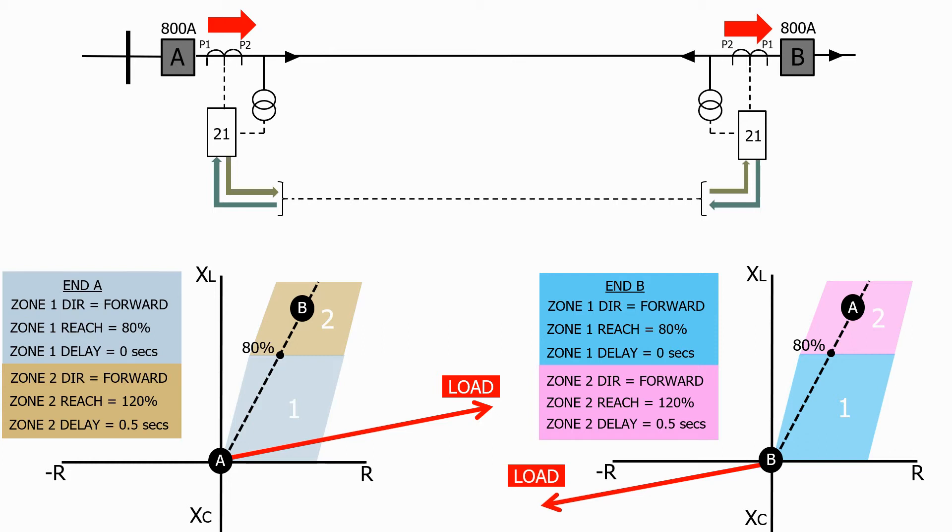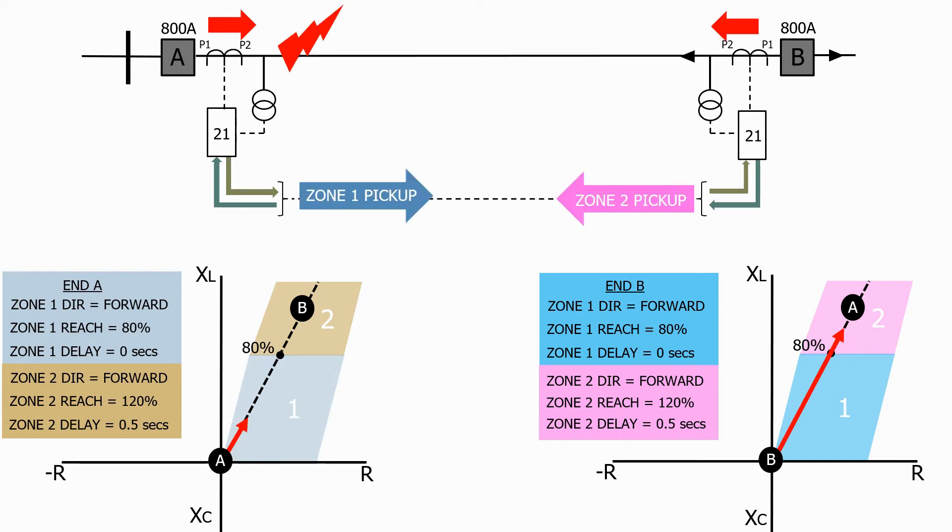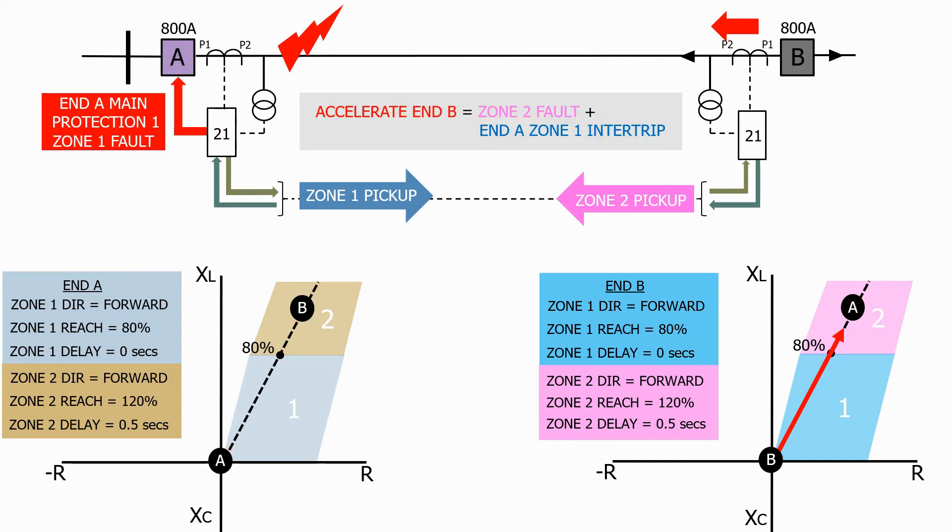Let's now add a fault in the first 10% of the feeder near to end A. On this occasion end A will see the fault in zone 1 and send the zone 1 pickup signal via the communication circuit to the other impedance relay. It also trips instantaneously on zone 1, clearing the fault from end A.